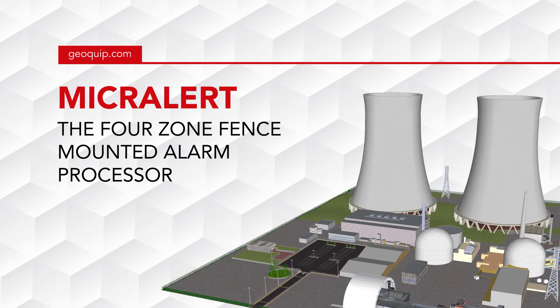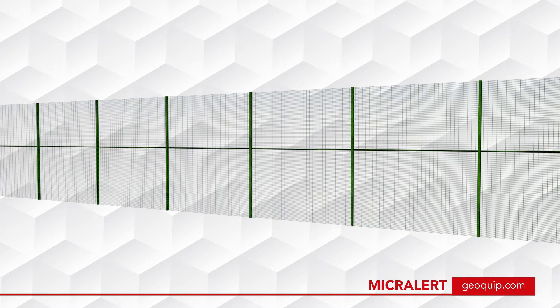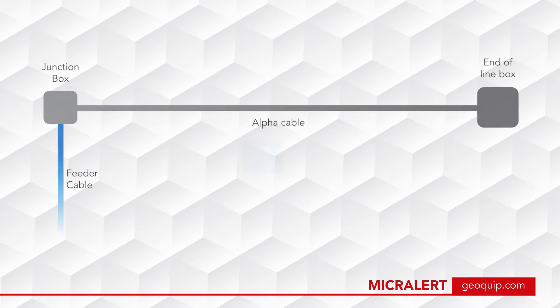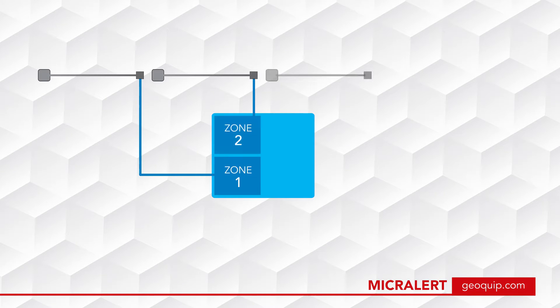Micralert is a fence-mounted detection system separated into four zones. Our proven alpha cable is fixed to the fence line of each zone to a maximum length of 200 meters. The alpha cable is connected from the junction box to an end-of-line box. A feeder cable relays the data from the junction box and alpha cable.